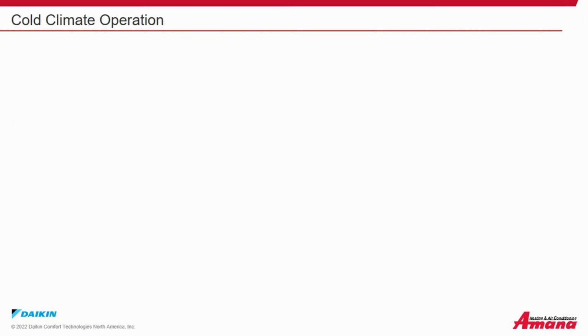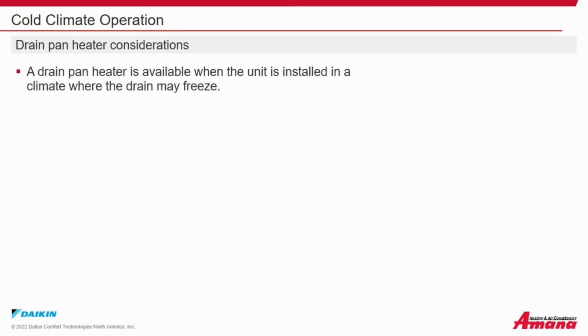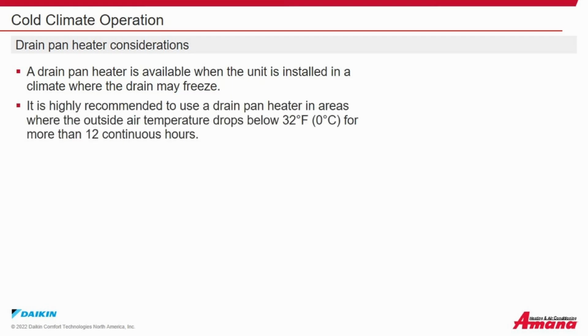Cold climate operation. Drain pan heater considerations. A drain pan heater is available when the unit is installed in a climate where the drain may freeze. It is highly recommended that you use a drain pan heater in areas where the outside temperature drops below 32 degrees Fahrenheit for more than 12 continuous hours.